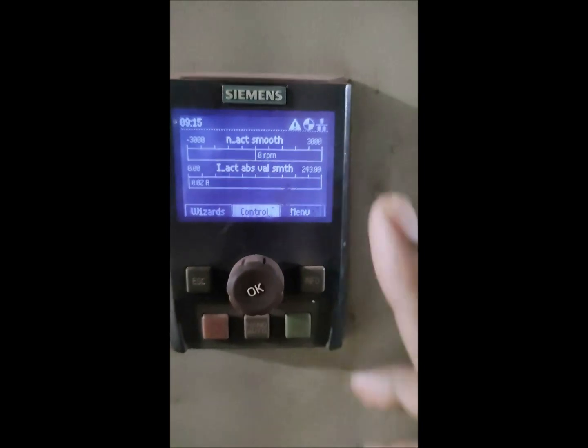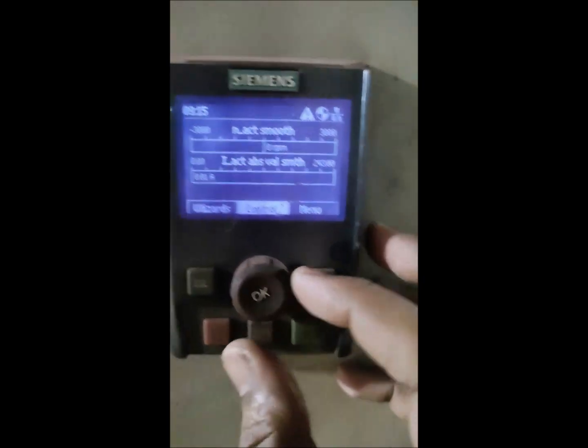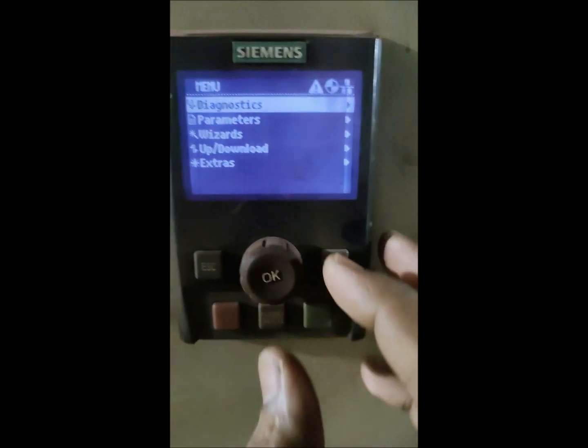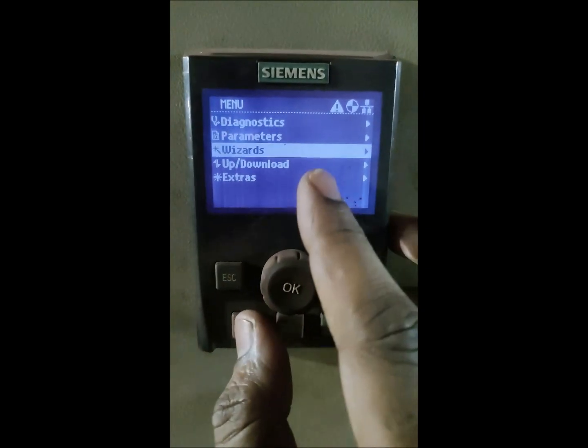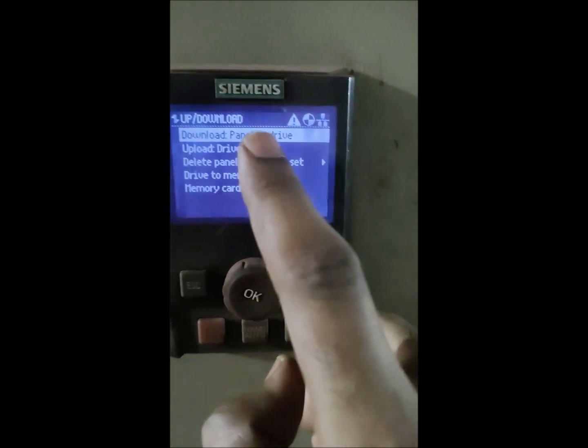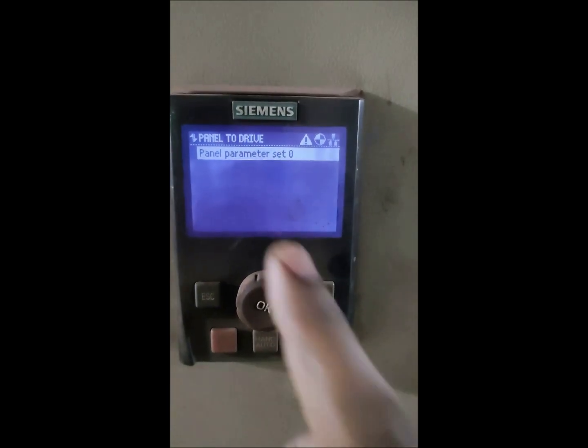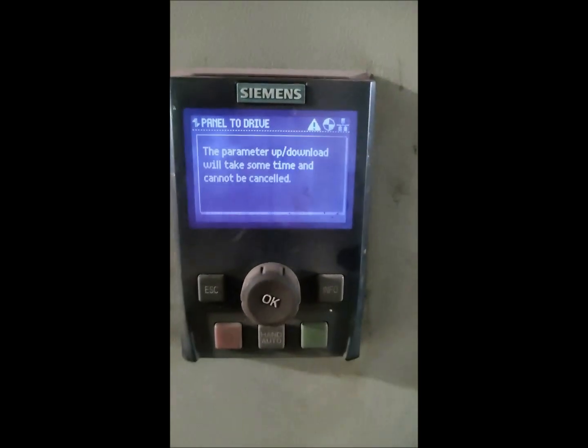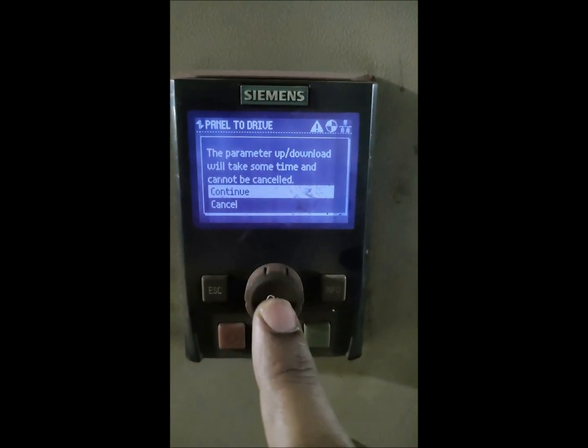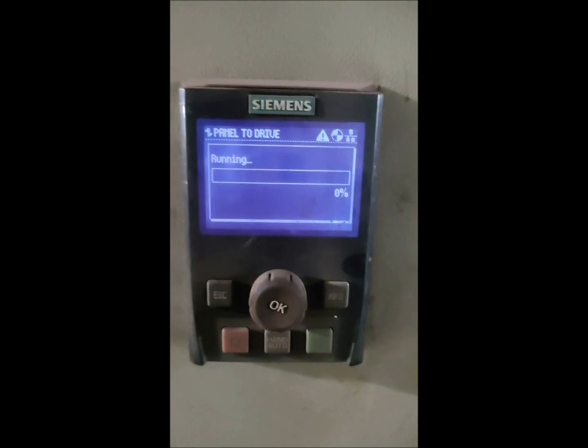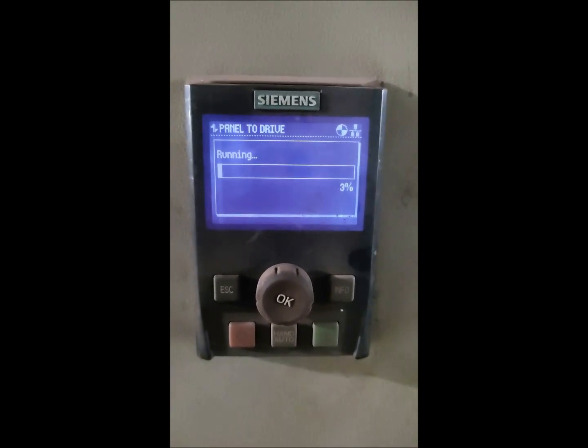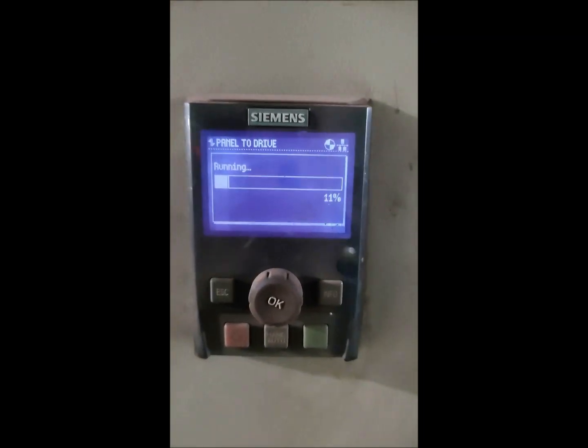So next we will take this panel and connect it to the faulty drive which we have done the factory reset on, and download the program - same process. We will go to the menu, upload/download, and now we have to download the program from panel to drive. So this panel will upload all the parameters to the drive. We select 'Continue' and it will take some time. The downloading process takes a little bit more time than the upload.